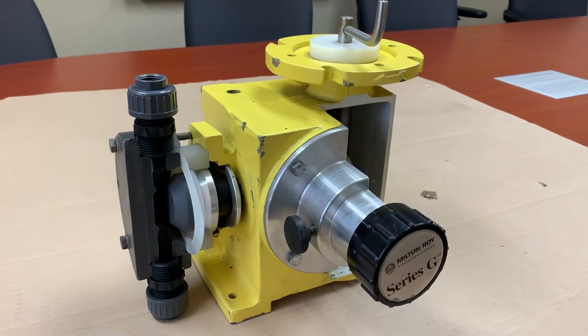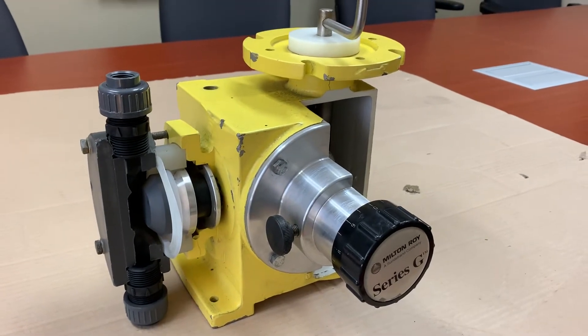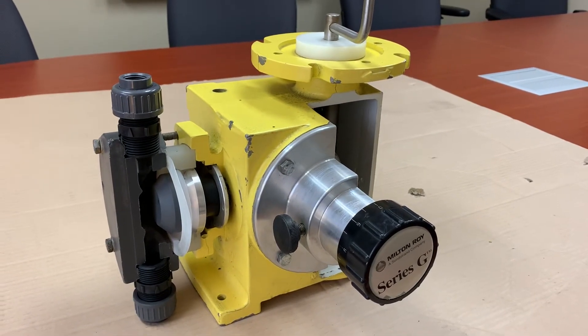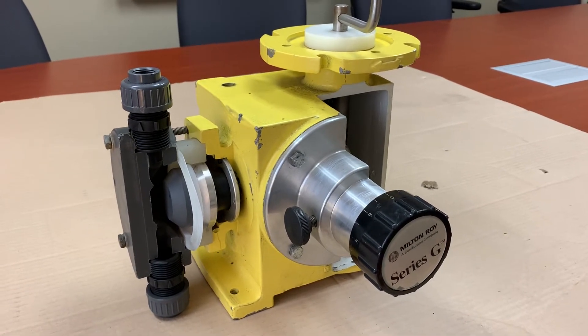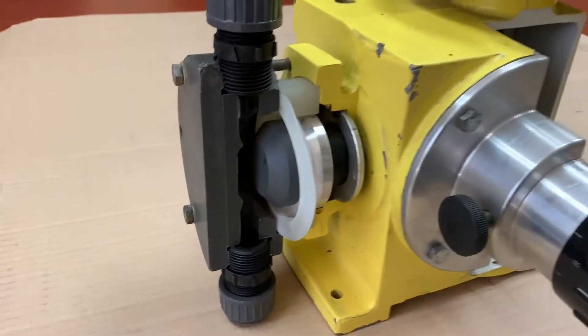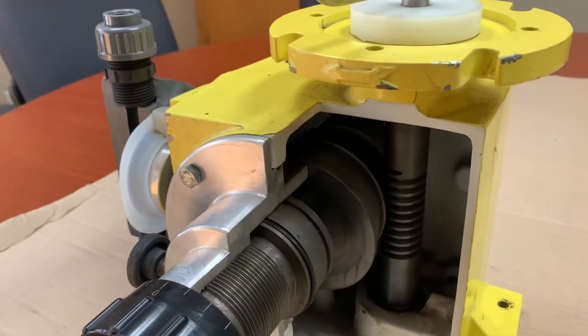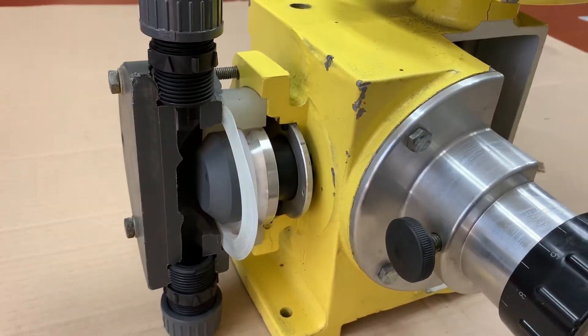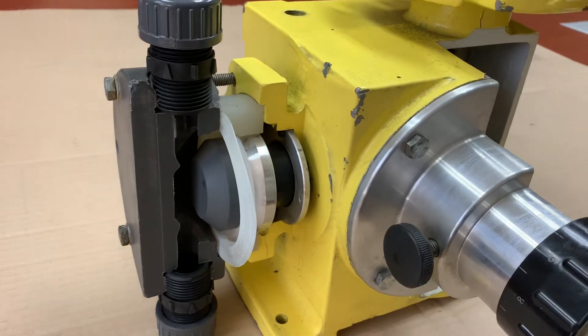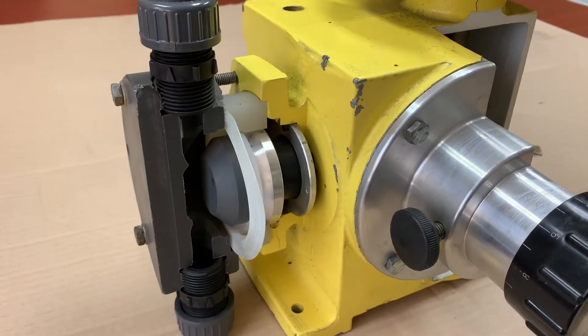Good afternoon, this is Josh with Pump Supply Incorporated. This is a brief introduction to the Milton Roy Milroyal G series diaphragm metering pump. The Milroyal G is a mechanically actuated diaphragm metering pump. That means the Teflon diaphragm is being acted directly on by a connecting rod attached to the gear train in the back. That compares to a hydraulic diaphragm where you'd be using hydraulic oil to actually move the diaphragm — here you're using mechanical force applied through the center of it to move it back and forth.